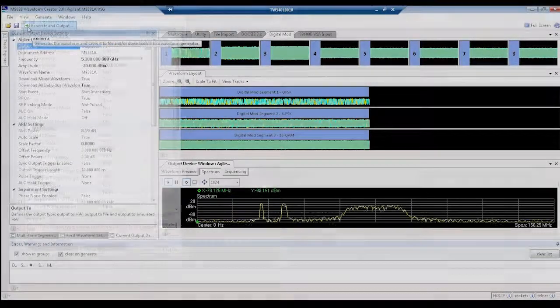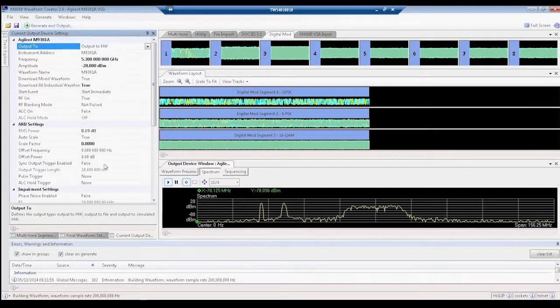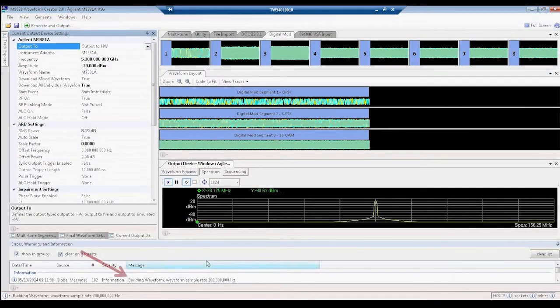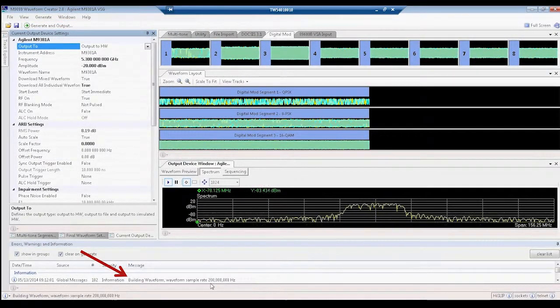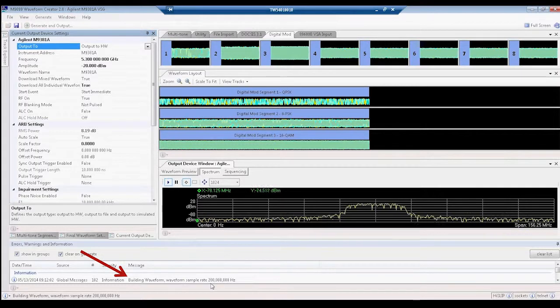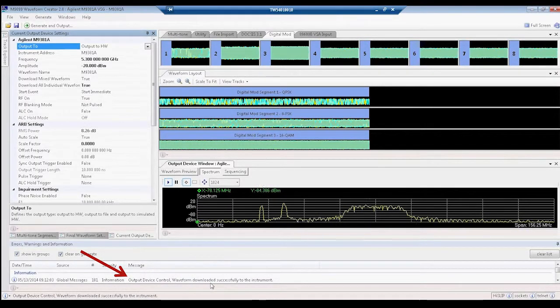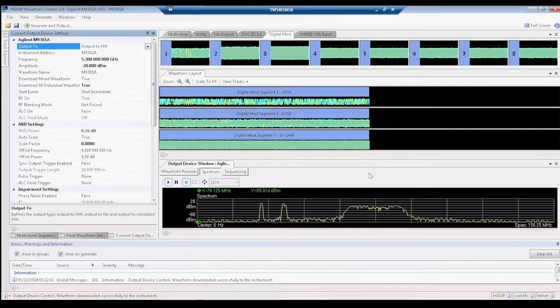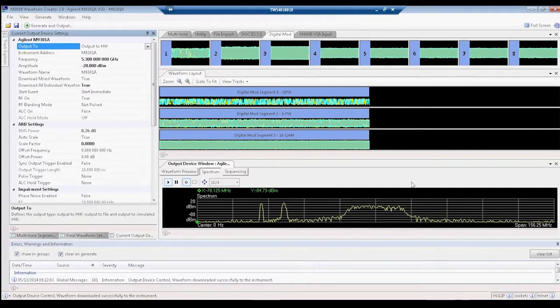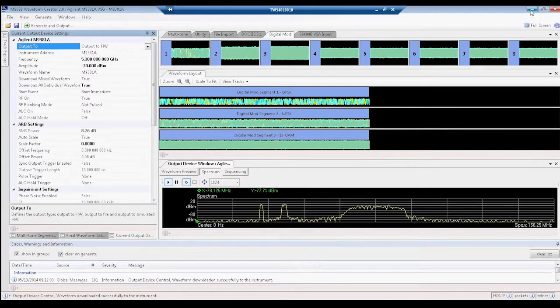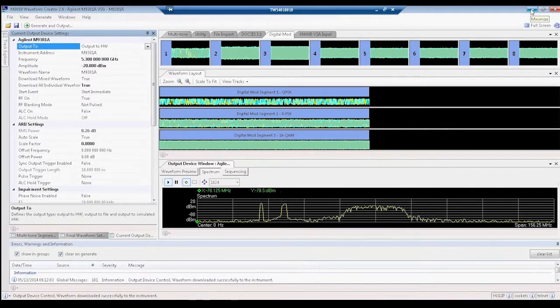Let's go ahead and select Generate and Output, and we'll see here that the message at the bottom says that it's building the waveform. Once it builds the waveform, it downloads it to the instrument. So now we should be having our three carriers coming out of the PXI VSG.